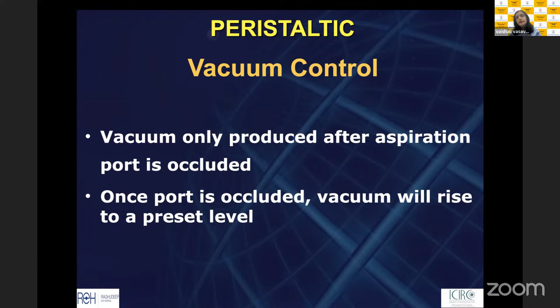Again, occlusion is the obstruction of the phaco tip. Only once the entire phaco tip is occluded by material or viscoelastic will the vacuum rise. One very important thing I want to bring out is that sometimes we inject a lot of methyl cellulose. In my beginning days, I used to use 2 syringes per patient. In my residency, I had loaded the eye with methyl cellulose, and then I entered with my phaco probe and immediately went to foot position 3. Foot position 3 is where the ultrasound starts working, and my entire chamber is full of viscoelastic. So if there was no lens material, nothing has been done, and yet I'm faced with the incision turning white. Can Aditi or Rishabh tell me why this would happen and what it would be called?